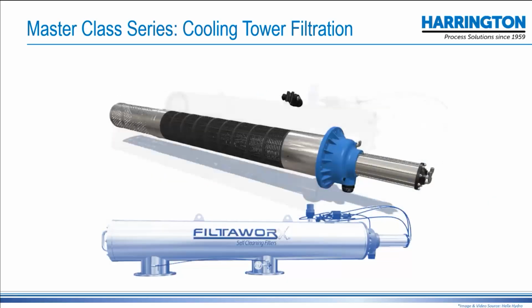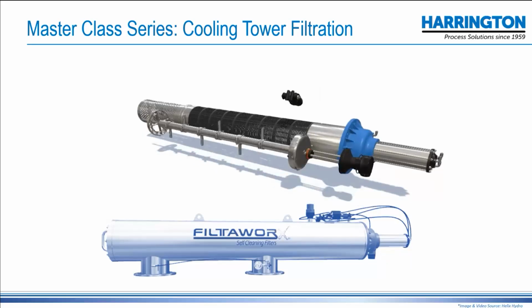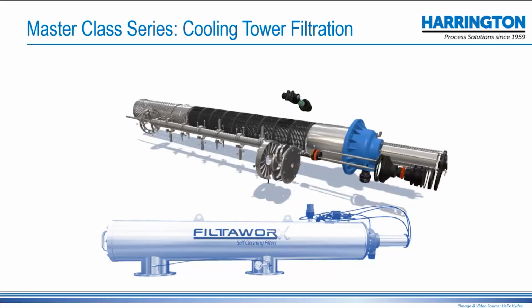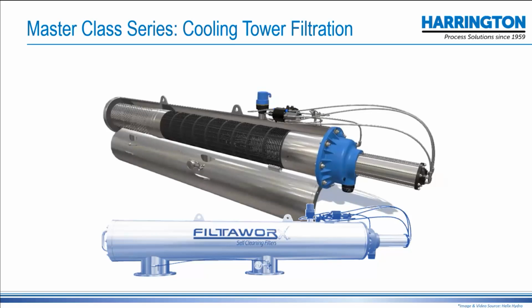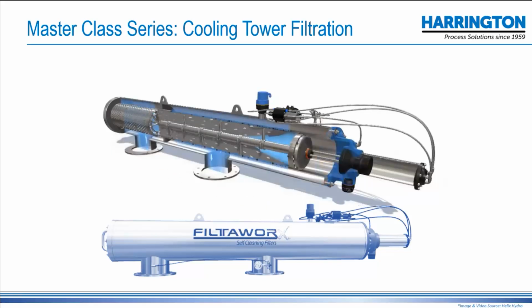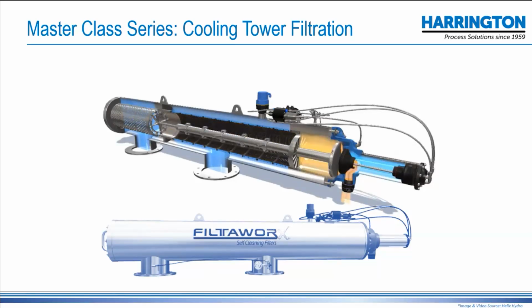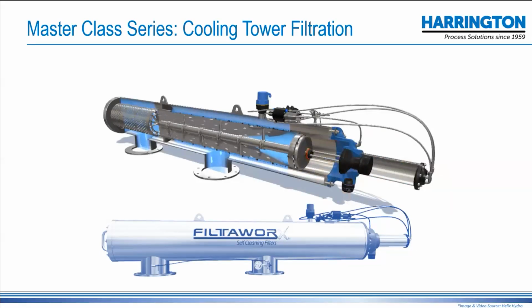The way these work is you have a coarse screen on the left, a fine screen to whatever microns, down to 10. Then the vacuum nozzle array has its own turbine. It's driven by water and a piston to move it back and forth. So as water is flowing through the screen on the left, it goes through the coarse screen, out through the fine screen, is filtered, as I said, down to 10. When it gets dirty, differential pressure triggers the cleaning mechanism, which moves the system forward and rotates it and vacuums the water to waste. And it never stops producing clean water while it's purging.